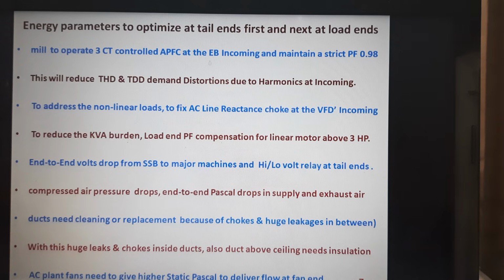Then coming to the non-linear loads, the line reactance choke needs to be fixed at the VFD incoming. Let us discuss with your VFD OEMs: whatever DC link choke they have given is not enough for the mill as such. The AC line reactance choke has to be mandatorily fixed on all the VFDs, so that at least 1/3 to 40% of the harmonics can be arrested at the VFD input itself.